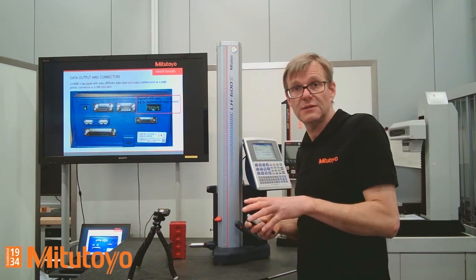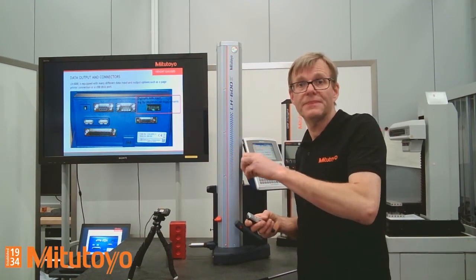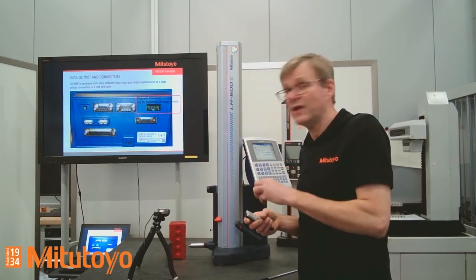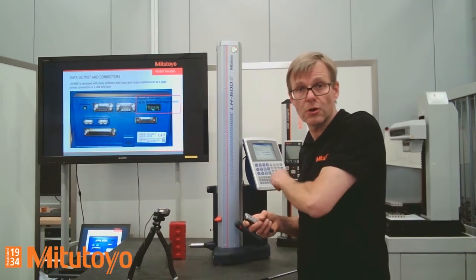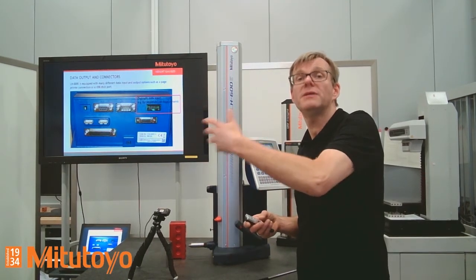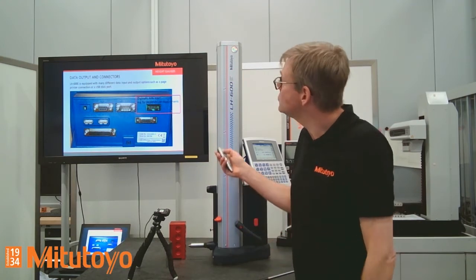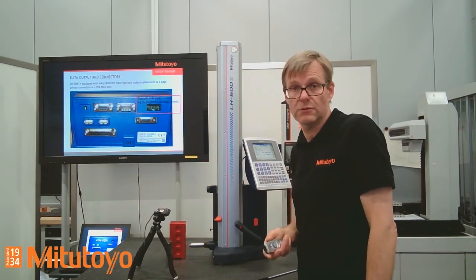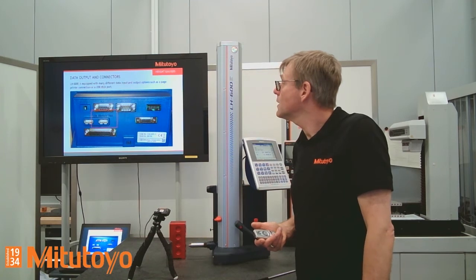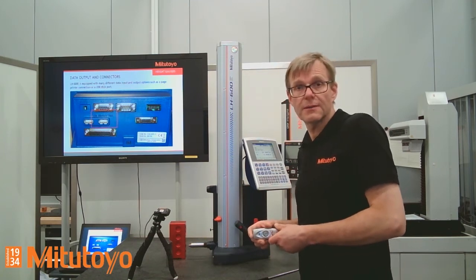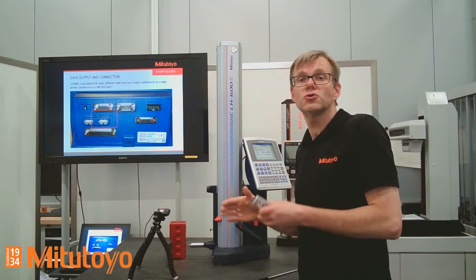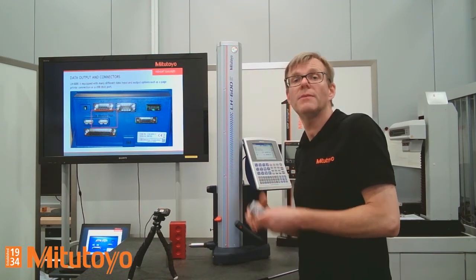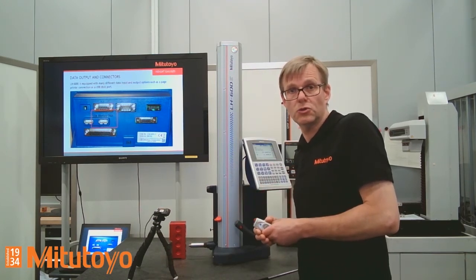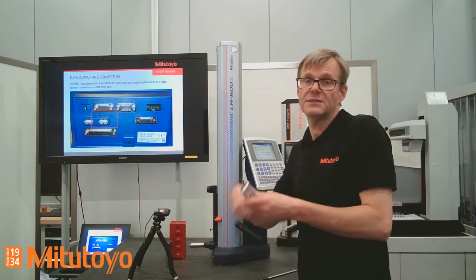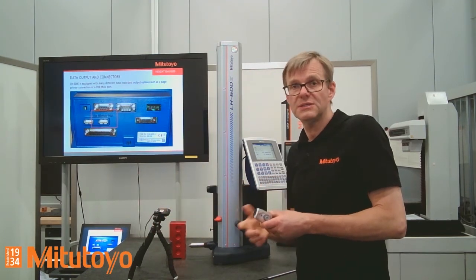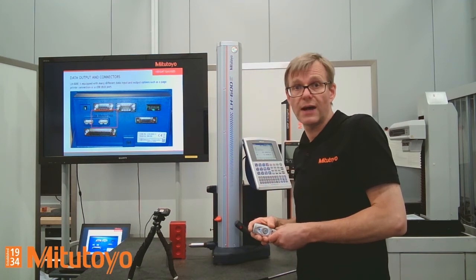You have already seen that I connected the cable of an indicator to the controller box. If we would like to make perpendicularity measurement, then I have to use the digimatic input connector. So this is a USB memory stick. USB memory stick can be used to store part programs on the stick or measurement results on the stick. So later on, you can go to the PC and send the data from the USB stick via CSV format to the PC.